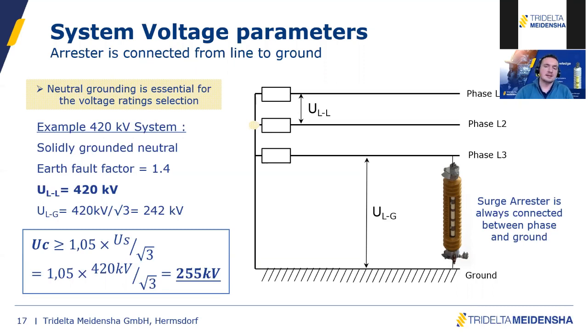The reason is that for a typical solidly grounded system, you have a low TOV value, and when your system is going through an impedance or is insulated, you normally accept a higher TOV value, and this is actually the main reason. So for a grounded neutral point, we use a typical earth fault factor of 1.4.